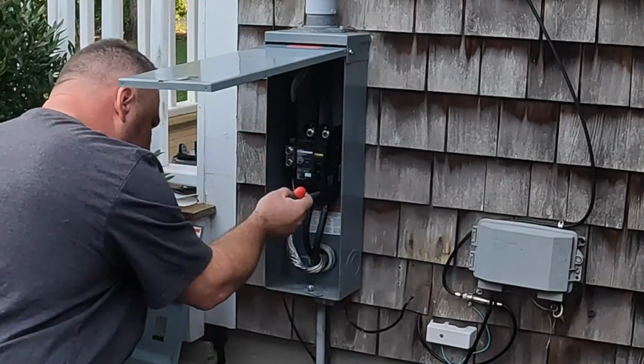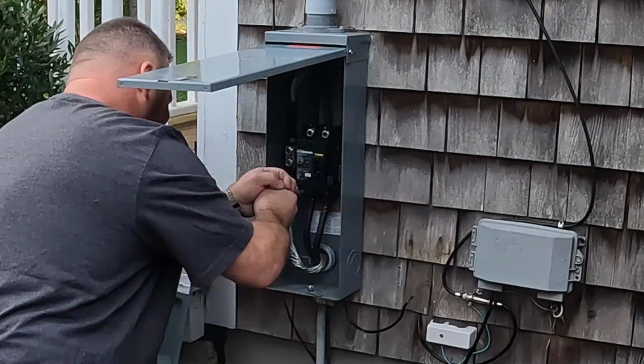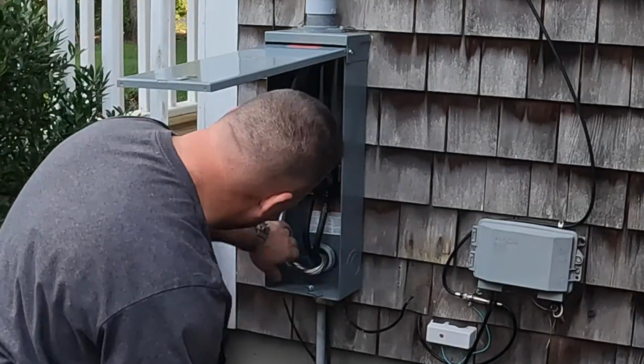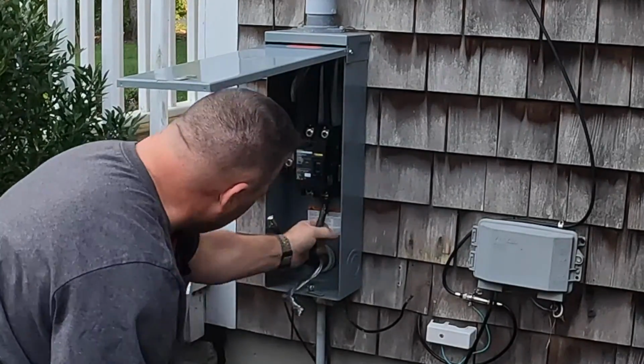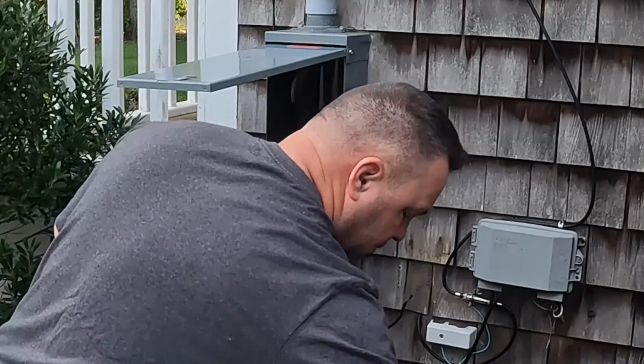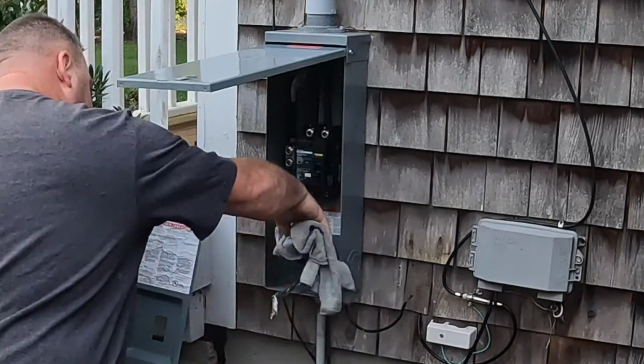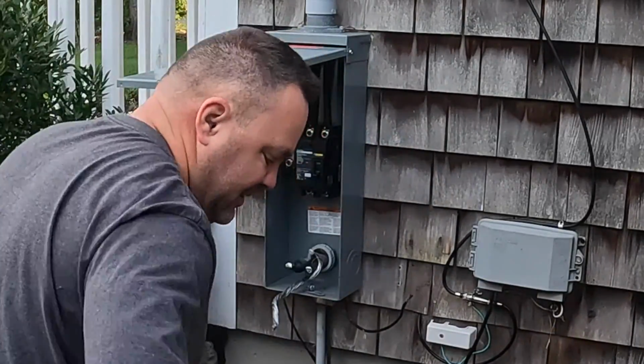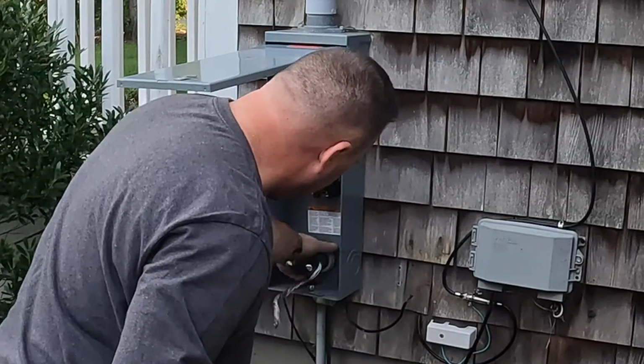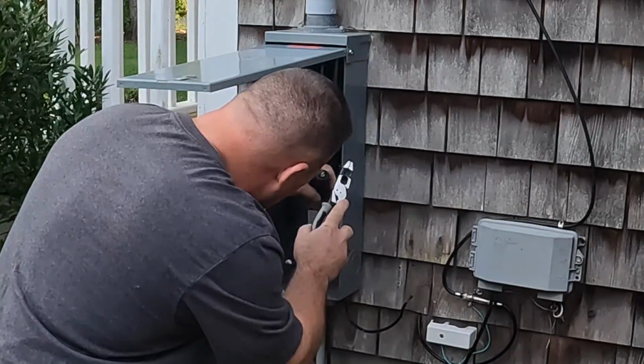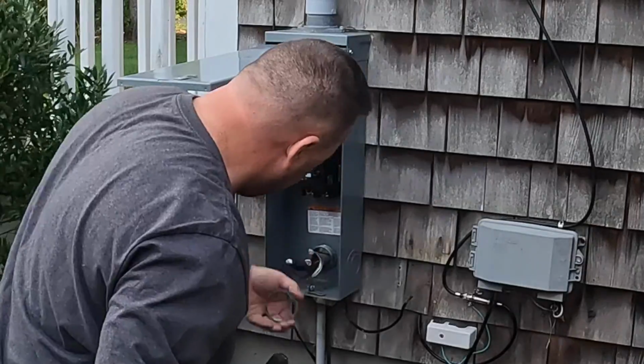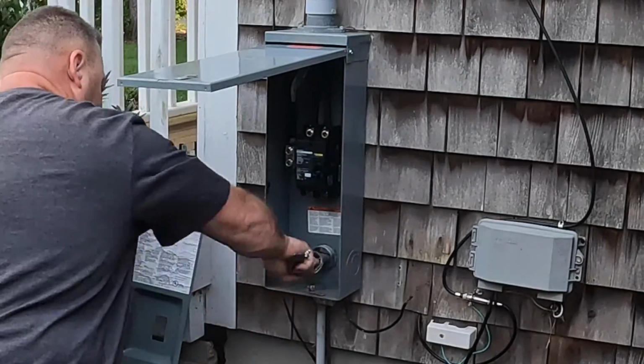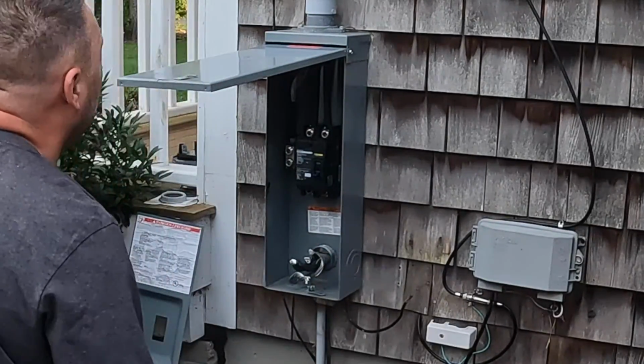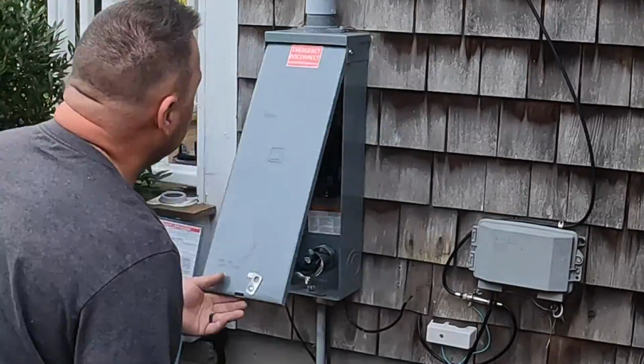This is a 200 amp emergency disconnect as required by the National Electric Code. When I originally did this service in 2020, I forgot that Massachusetts was using the 2020 code already. And at this time in New Jersey, we were still using the 2017, so we did not have this requirement. So I upgraded the service, did a really nice job, and then found out that it didn't pass inspection because it requires this emergency disconnect.